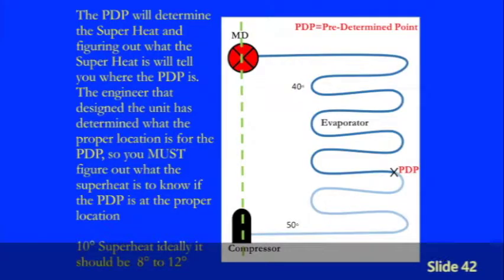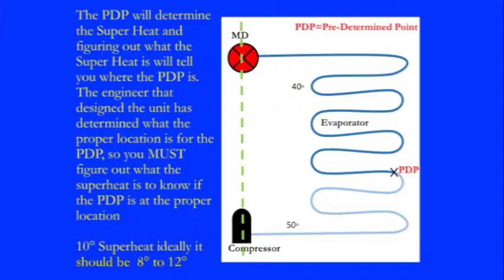Let's look at slide 42. We see the pre-determined point is right there on the coils, where the engineer wants it to be. The pre-determined point determines where the superheat is. If the pre-determined point moves, that's going to change the superheat.